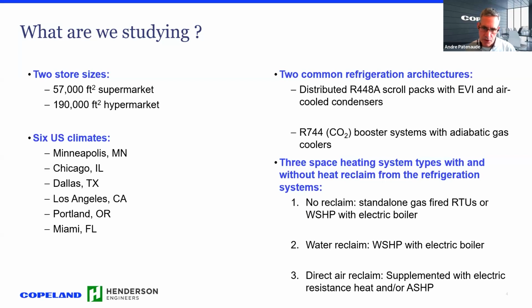And then Trevor will talk about these in more detail, but 3 space heating types, with and without heat reclaim from the refrigeration systems, were evaluated. So the baseline system was no reclaim: standalone gas-fired rooftop units, or water source heat pumps with electric boiler. That was number 1. The other one was reclaiming heat from water, and water source heat pump with electric boiler. And then the last one was direct air reclaim, so using that CO2 to reclaim heat directly, supplemented with electric resistance heat and/or air source heat pump. And as I mentioned, Trevor will go through these in detail. Next slide, please.